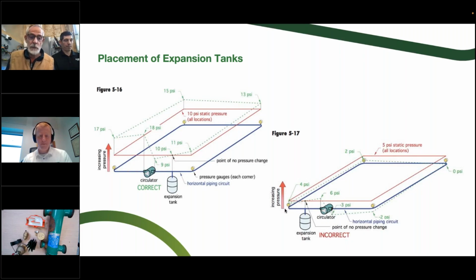But here's an example. This is an old Bell and Gossett drawing from 1960 something, I believe. What happens is when we pump at the point of no pressure change, the circulator is making its pressure difference from the suction side, from the inlet side, because it can't push water into the expansion tank. It can't compress it. It can't take water that's in there and squeeze it and make it smaller. So it says, well, the only way I know how to operate a circulator is I've got to make a pressure differential. So it's taking it from the suction side.